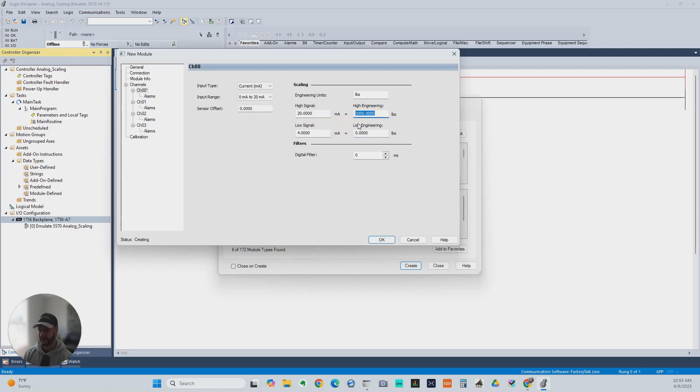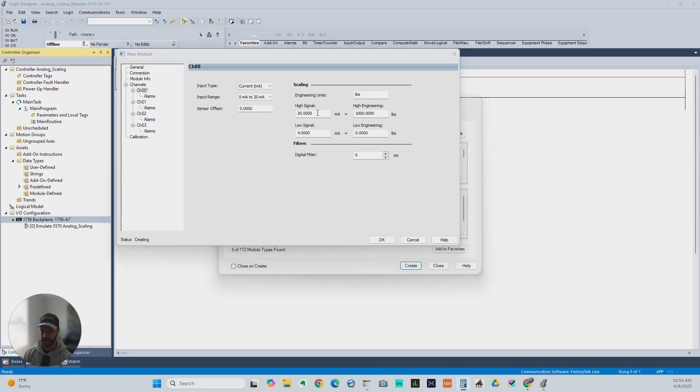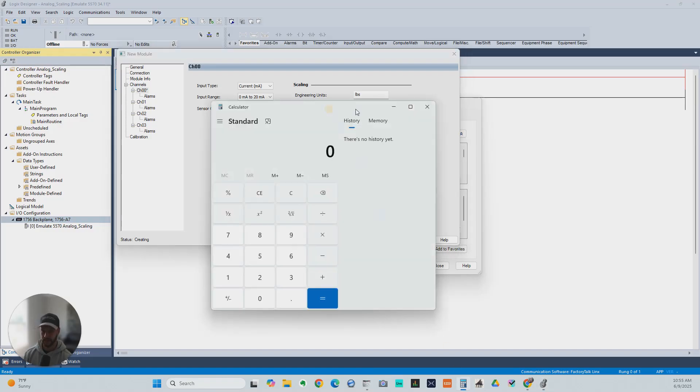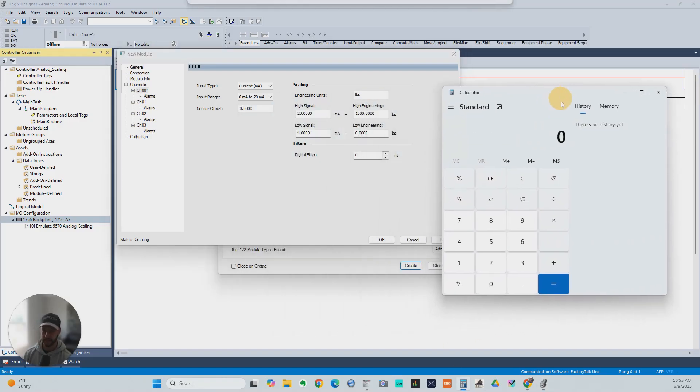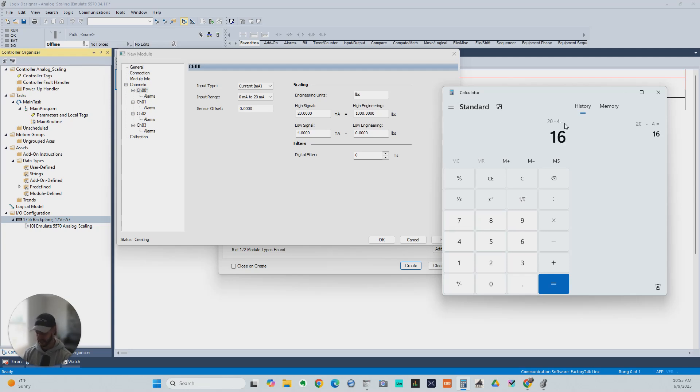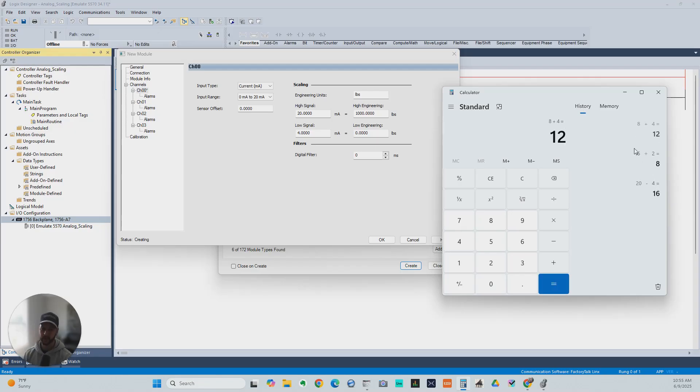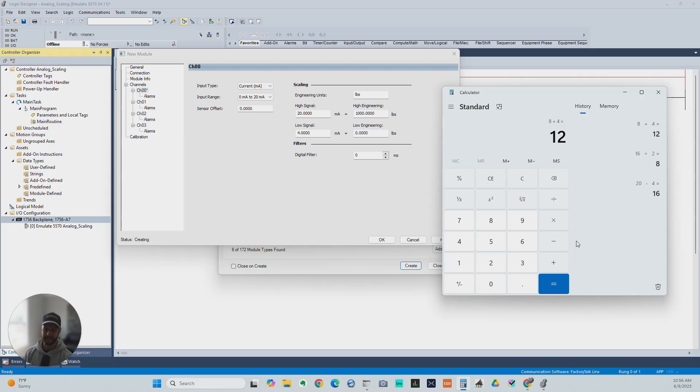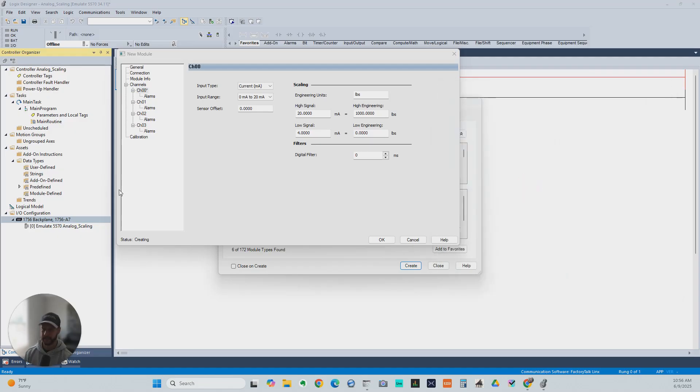Off the top of my head, I don't know what 50% would be. 0 to 1,000, 50% of that is 500 pounds. So that's going to be somewhere in the middle between 20 and 4 as far as the milliamp signal we would expect. 20 minus 4 is 16 divided by 2 plus 4. So 12 would be the halfway point between 4 and 20. I should have been able to do that off the top of my head, but I forgot. So 12 milliamps would equal or should roughly equal 500 pounds.